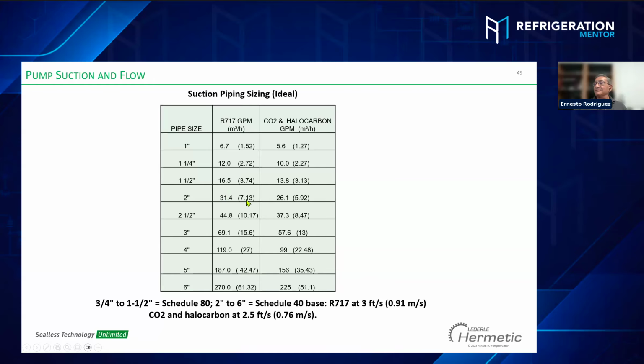For example, this is the suction. Let's go back to the example I have in South America. Okay, they replaced a Buffalo pump. They installed my pump, 75 gallons per minute. I say, okay. They call me and say the pump is not increasing pressure. I say, what do you mean, not increasing pressure?